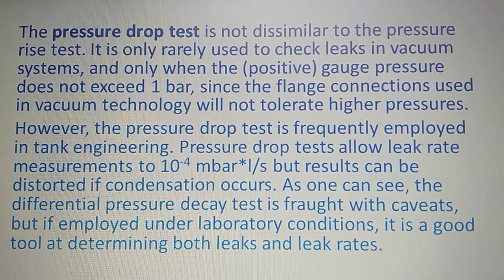This is a very high technology test, and it must be noted that the only credible method to detect leaks smaller than 10 to the power minus 6 millibar is with a vacuum leak detector. So this test also has a drawback, because this test is only used to measure a very high vacuum or a very low pressure.